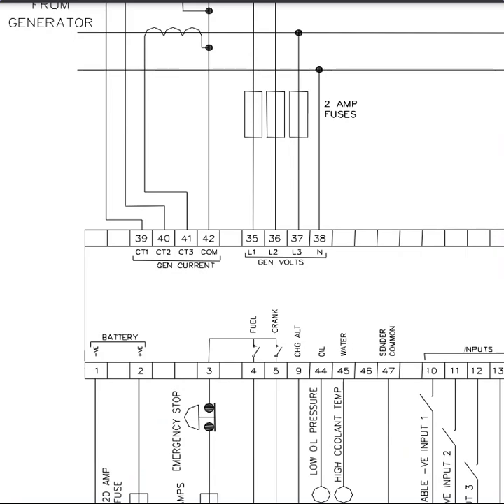That's where, when you're using the load bank, you look at the steps that it has. It could be a 5 kW step, and as you get to the bigger load banks, the towable ones, you're going to have 50 kW steps, maybe even 100 or 200. You ultimately need experience doing all of the load bank sizes, a 100 kW suitcase, then the 250 kW, and eventually the 1 meg towable trailer load banks.